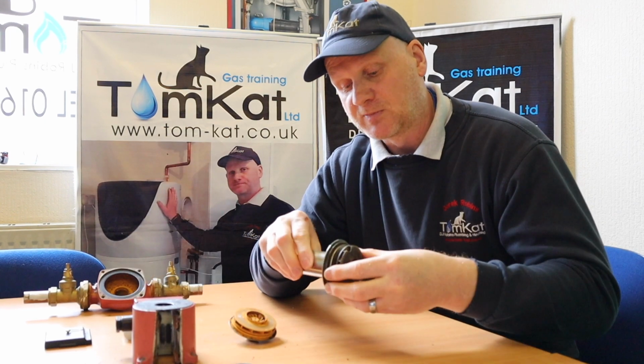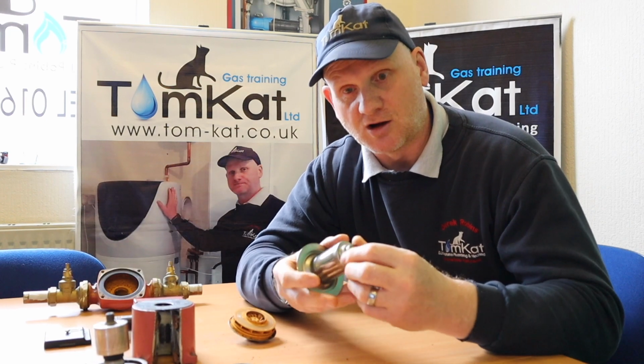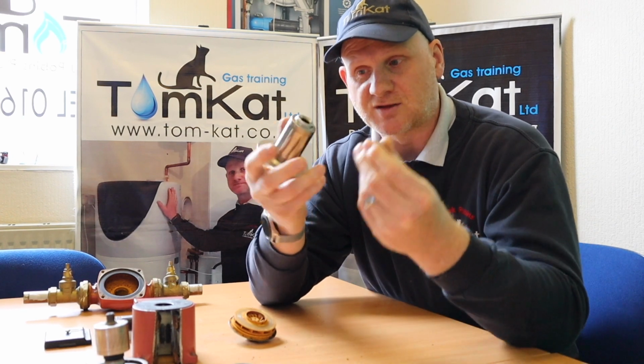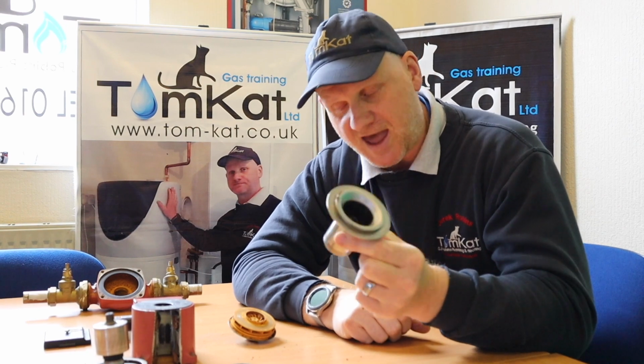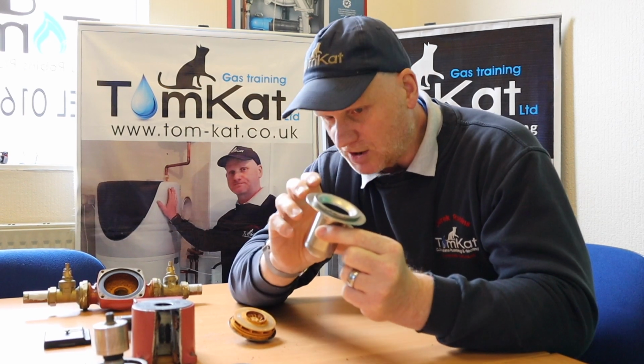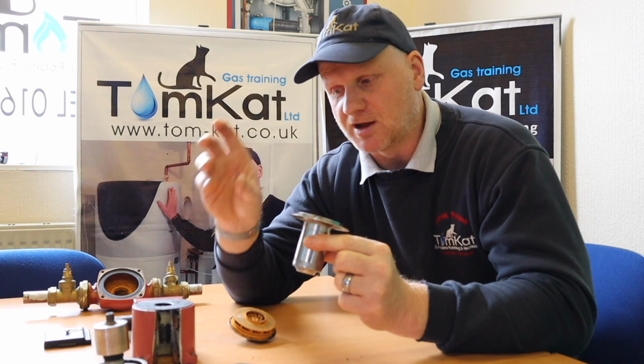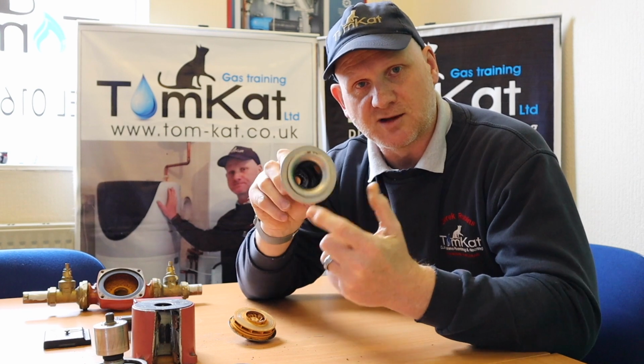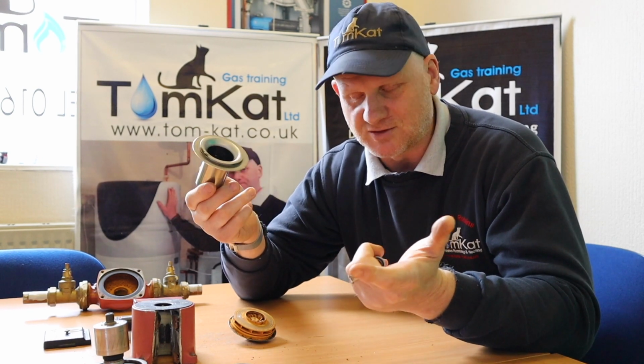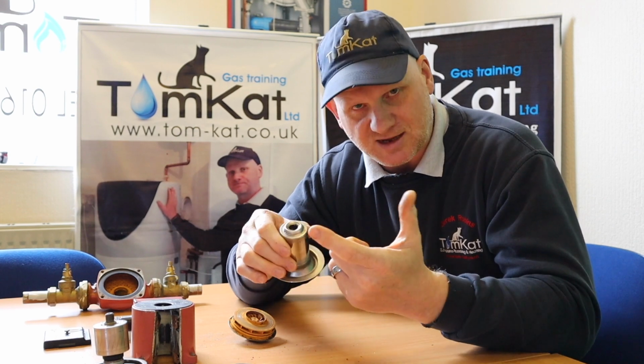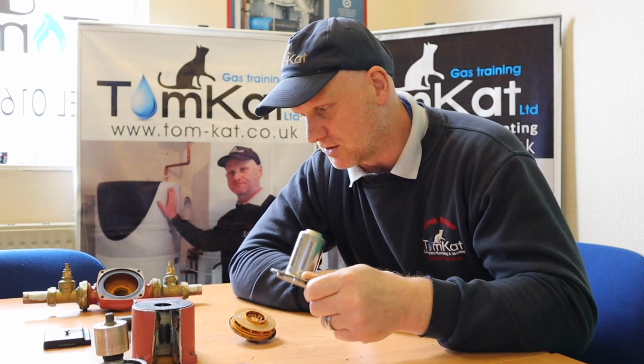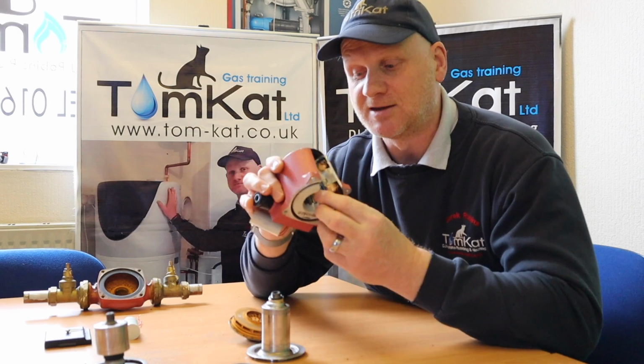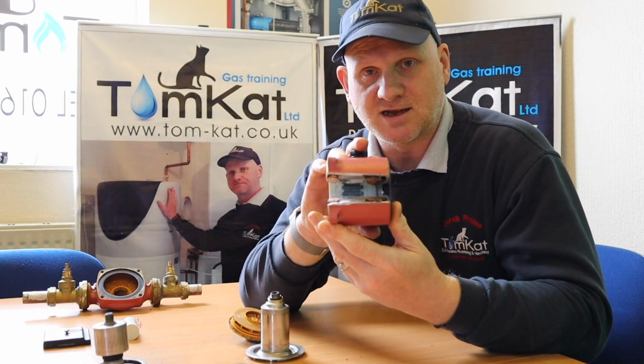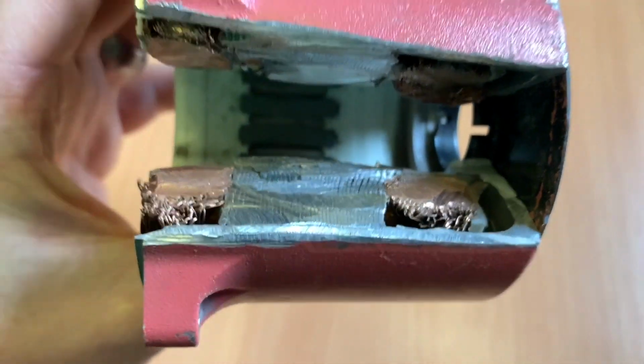Now the bleed screw is in the end of the bell housing. So you can see the bleed screw there, and that's how we get rid of the air to fill this bell housing with water, so it allows the magnet rotor to keep lubricated. And this is where the boiling of the water occurs, which then turns to steam, which is when you release this, sometimes you get the steam coming out. Okay, so you've got to be careful because it's 100 degrees. That's pretty much how it's laid out inside here. And the little cutaway there, you can see it quite clearly now how this is put together.